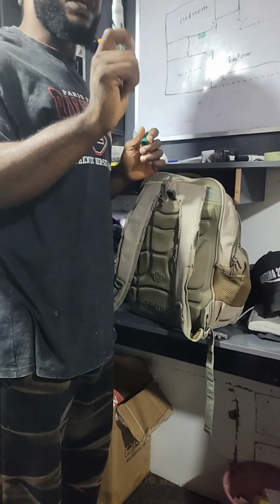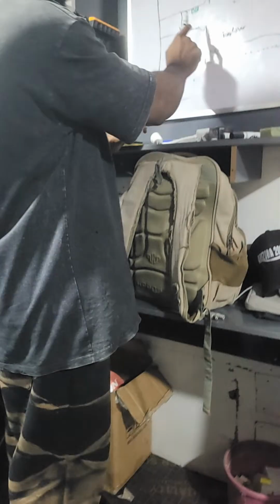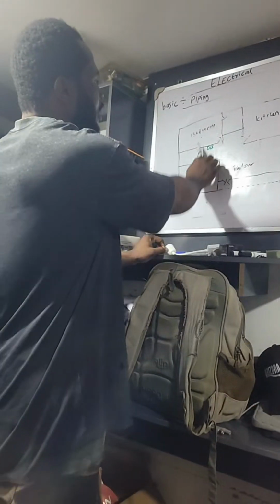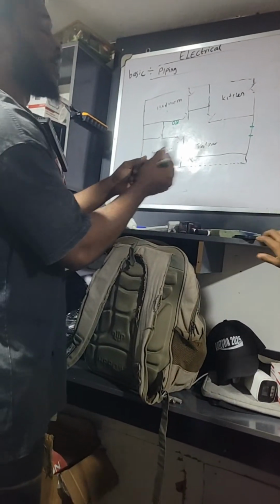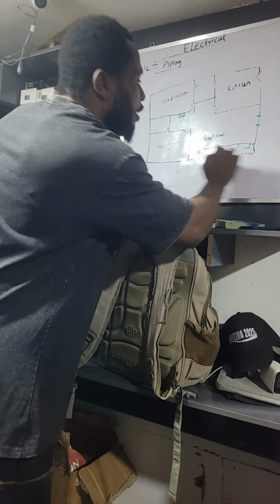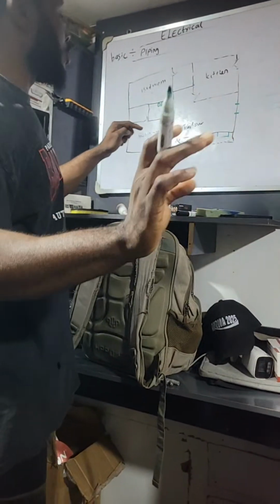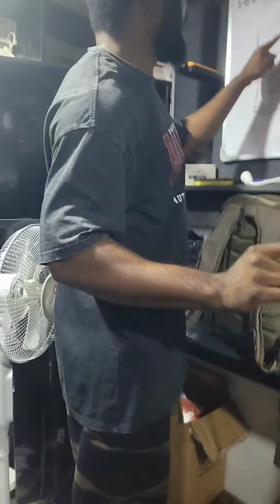The first thing you consider is cable. That is first. You do cable consideration first. So you consider how your cable can easily network to the DB. It's not as if, let's say, for example, this is here, this is here, kitchen is here, and then because you are trying to do one or two things, you go and put your DB here. You didn't consider cable for your customer, because you need to keep your customer in mind. Then when you are wiring, you start wiring from this point to this point, from this point to this point.